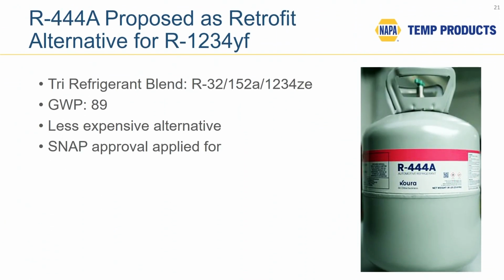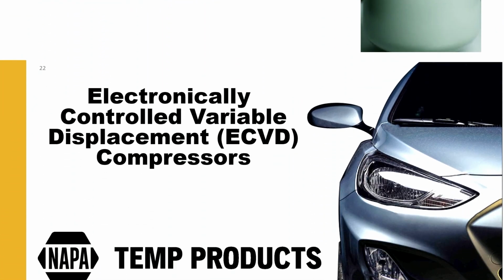There is also a proposed retrofit refrigerant alternative for R1234YF. It's called R444A, and again it's another blend of refrigerants. You see the blend content here. The whole idea is, again, it hasn't been approved. It's at the EPA under the SNAP program, maybe approved later this year. The whole idea here is just to have a less expensive alternative available, a less expensive alternative for R1234YF, which, as you know, is still quite expensive.